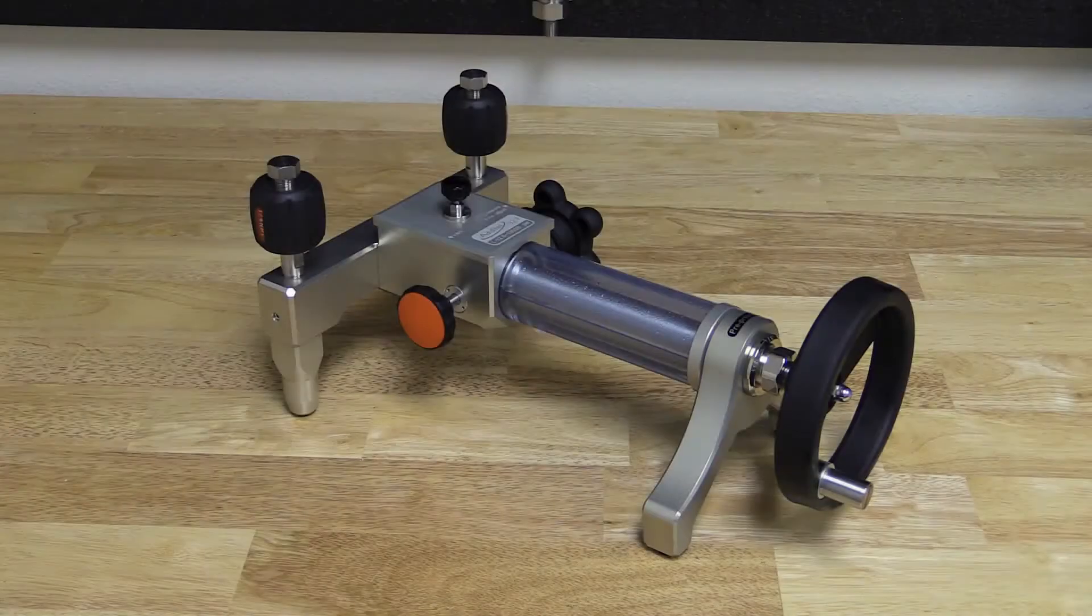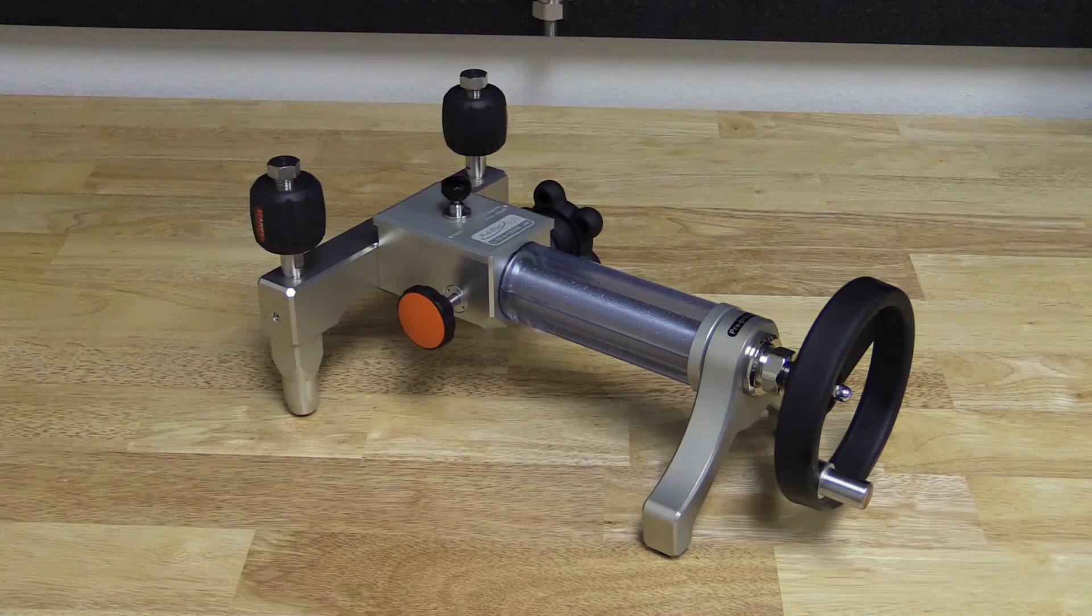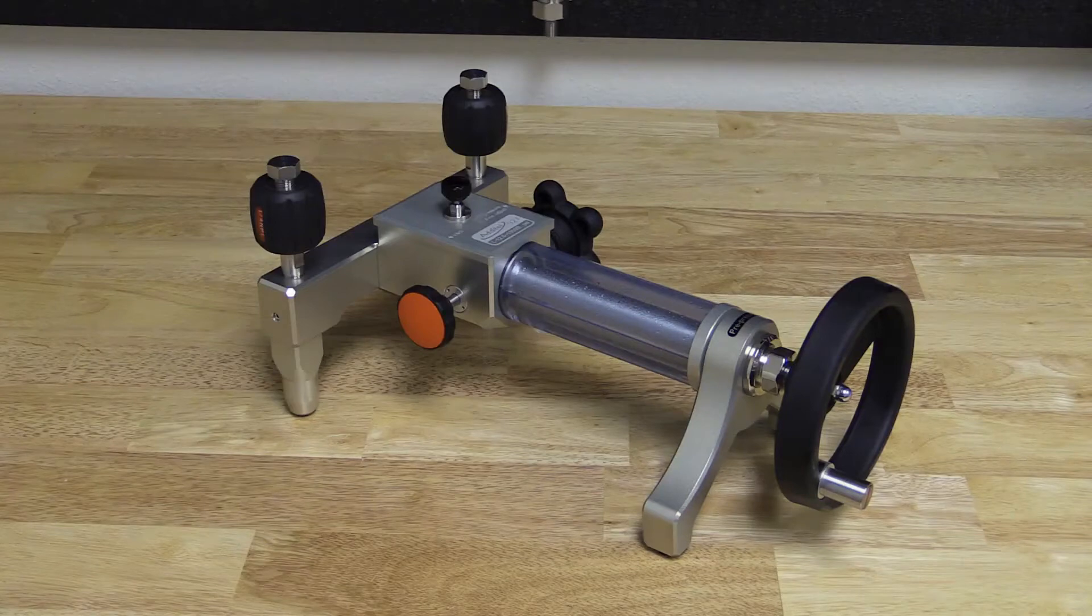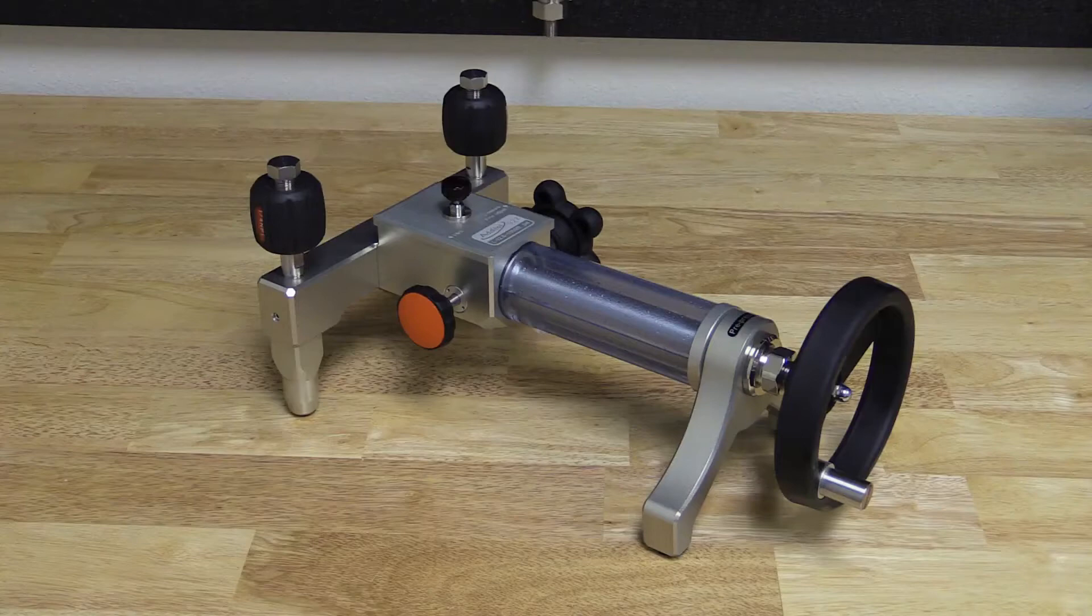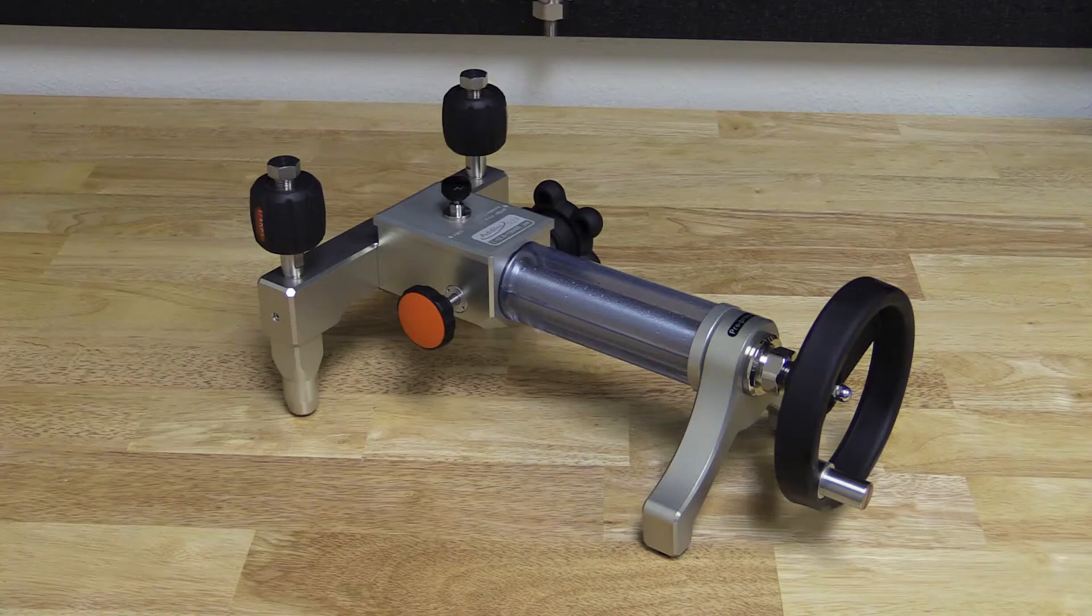To produce stable and high pressure measurements using a hydraulic calibration pump, the gas within the calibration system needs to be removed. Hydraulic test pumps use various types of fluid to generate high pressures. Because gas is more compressible than liquid, purging most if not all the gas out of this system will allow for maximum pressures to be generated and the best stability to be realized.